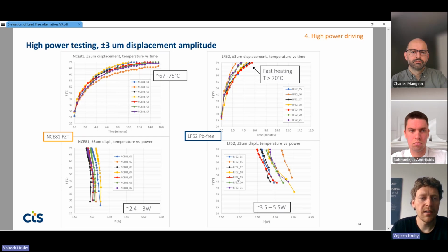So moving to the final driving scenario, which was ±3 micrometers displacement. In this case, we only tested LF52 and PZT transducers. This was because the PZ12 transducer, the lead-free one, was heating too fast, so it wasn't really a point to measure it in this scenario. And we see that the PZT transducer reached 70 degrees between 10 to 15 minutes. And with the LF52 lead-free alternative, we reach 70 degrees between, let's say, 3 to 6 or 5 minutes.